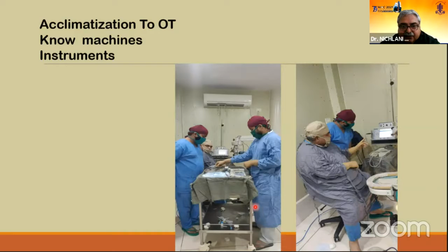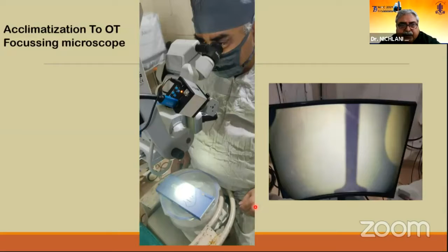This is a very important step: before operating, you must focus your operating microscope, because if a variety of surgeons are focusing the operating microscope, then definitely there will be a change while you are operating any case. So before you operate, try to see that the focus of the microscope is perfect or not. Change the eyepiece setting according to your need, and later on you can definitely mark those settings with your own calibration.